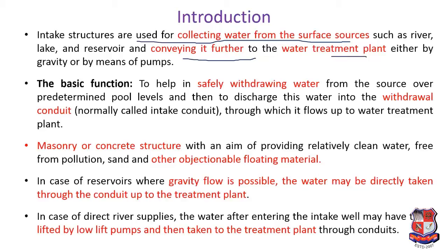Now there are two possibilities for the flow of water to the treatment plant. First is by means of pumping, if your water treatment plant is above your water source, and second is through gravity, if your water treatment plant is below your surface water source. And mind well that these intake structures are only provided for the surface water source, not for the subsurface water source.